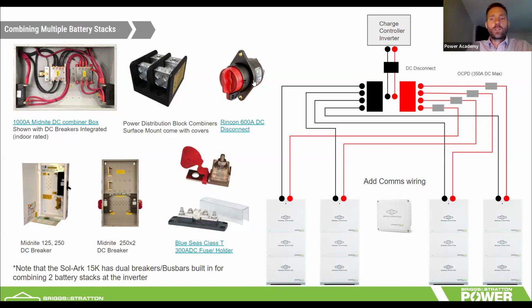It's not always required, but some jurisdictions require a DC switch between the battery bank and the inverter, and you can use these Rincon UL listed DC disconnects that are rated up to 1,000 volts. I caution you about using cheap disconnects that are rated to too low of a voltage. You'll want to make sure it's rated to a higher voltage. And Rincon makes a nice UL listed example for under $100.